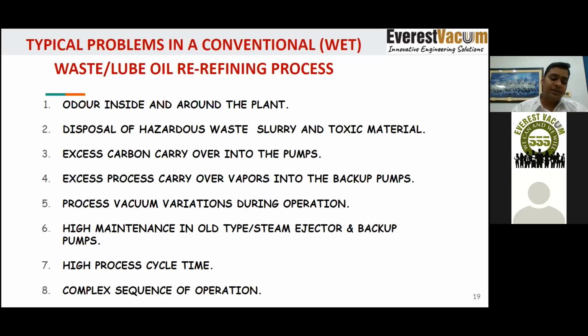Complex sequence of operation. Since we were opening one ejector after another ejector, then a third ejector, controlling the steam flow everywhere, opening the valves, closing the valves, partially opening the valves, it led to a lot of complex sequences of operation. Sometimes we miss something and it leads to damage in the process, with complete batches going off production. It was very troublesome to maintain these kinds of operations in earlier days.